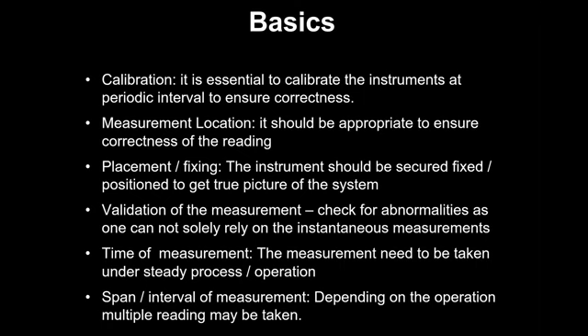Now we'll come to some basic requirements when we are doing measurements or when we are handling the instruments. First is the calibration. Calibration is essential, because what we do is send the instrument to a recognized laboratory, maybe having traceability with the NABL certified instruments. What they do is send their master calibrator instrument to the NABL accredited laboratory to get it tested, so that their master calibrator is accredited by NABL. So it has traceability, in that it is calibrated against an instrument calibrated by NABL. So that is the calibration. When we are sending the instrument for calibration, we need to check the accreditation of the calibration agency, because there are many people who will just give a certificate without even receiving the instrument.